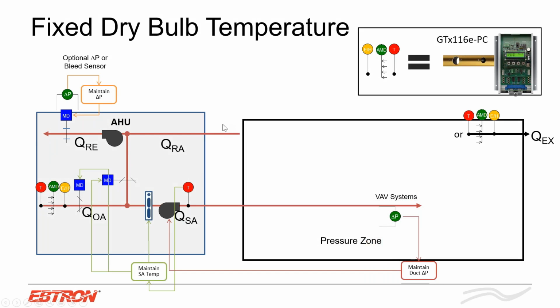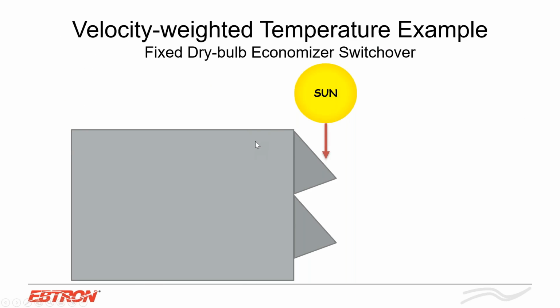Let's look at some economizer strategies. Now, it doesn't matter what type of economizer strategy you're using. If you're installing the EBTRON product, again, you can use the temperature sensor as an output, and you can also use the humidity sensor if you need that. So this is a fixed dry bulb temperature economizer control strategy. And let's look at this, and let's look at how EBTRON actually calculates their velocity weighted temperature, and show you how it gives you a really accurate representation of the duct. So we have the sun hitting down on this dual ducted outside air intake, flow coming in.